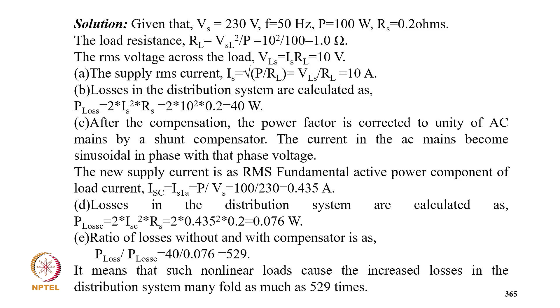After compensation, the power factor is unity by the shunt compensator. So current in the AC mains becomes sinusoidal and in phase with the supply voltage. The supply current RMS, active power component, is IS equal to P upon VS, so it's 0.435 ampere, and losses in the distribution system are calculated as 2 IS squared RS, so it becomes 0.076 watt. The ratio of losses without and with compensation is 40 upon 0.076, that is 529 times. So it means that losses in distribution are manifold, as much as 529 times.